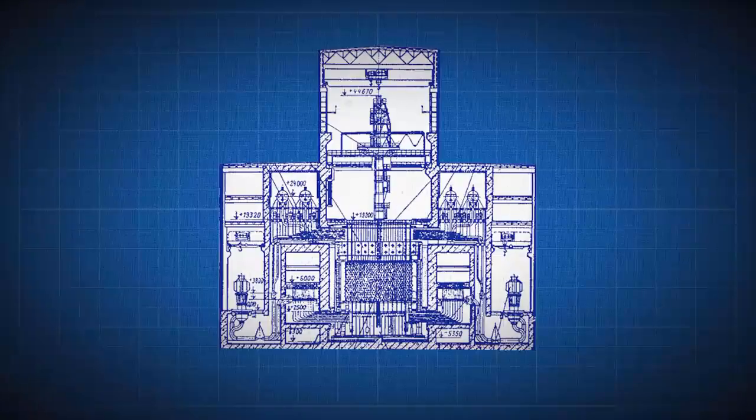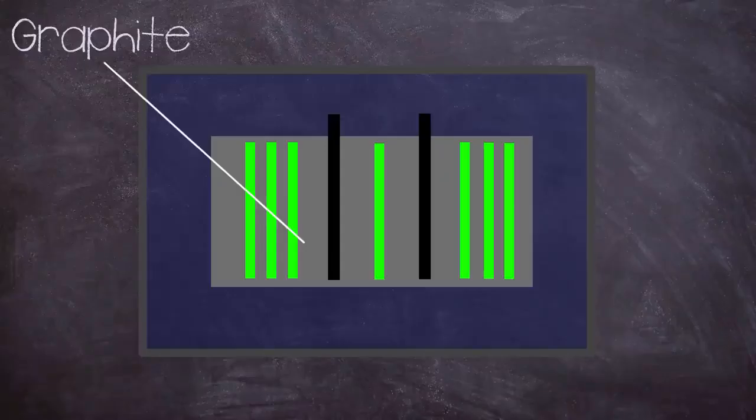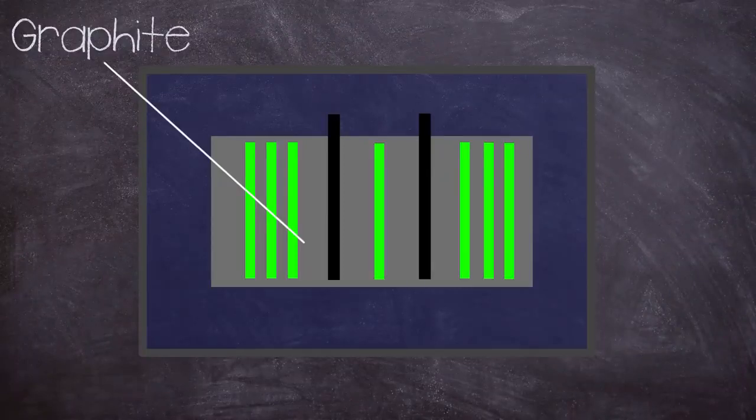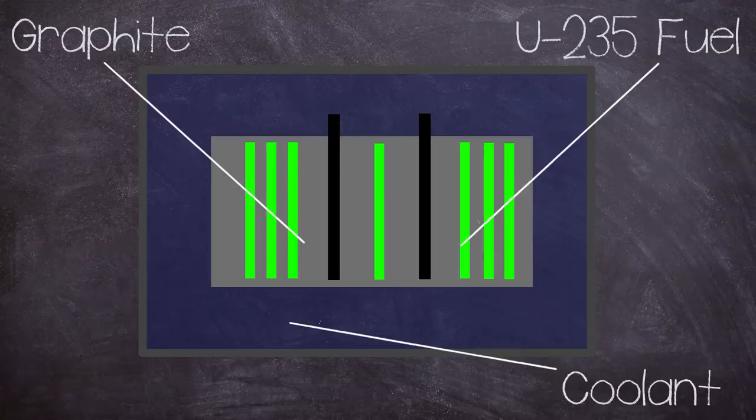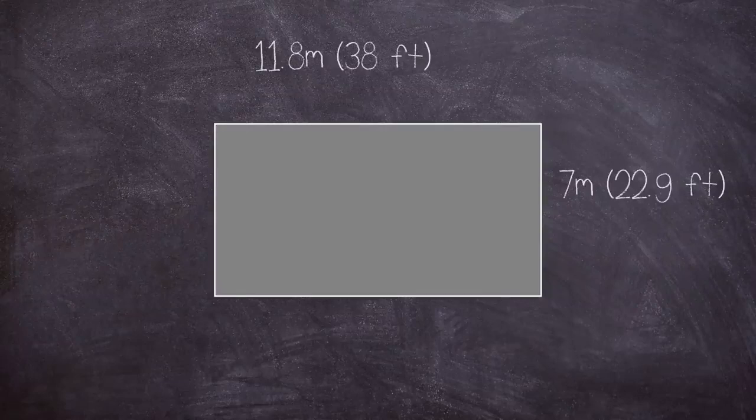The RBMK was a unique design that used graphite to moderate the chain reaction with light water as coolant. This combination allowed it to use lower enrichment uranium-235 for fuel, which was significantly cheaper. The RBMK had a very large core region of seven meters height and 11.8 meters diameter, mounted in a steel cylinder placed on top of a biological shield. The steel cylinder was 16 millimeters thick with diameter of 14.52 meters by height of 9.75 meters, inside a reinforced concrete lined pit.